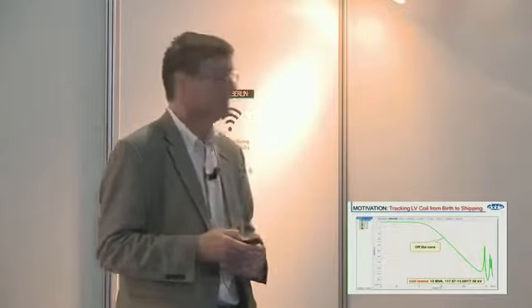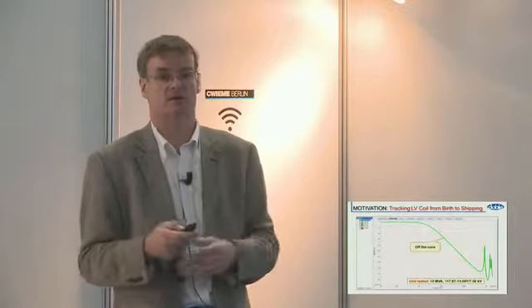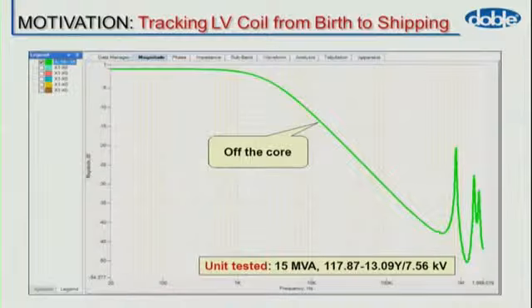One of the tests for transformer integrity is SFRA, sweep frequency response. It tells you about the mechanical integrity of a transformer. And we can look at the coil and the response, and we can see how they change over time. SFRA is a very, very good tool for detecting movement. It's also a very good tool to detect people who are not very good at field testing because they get the results wrong.